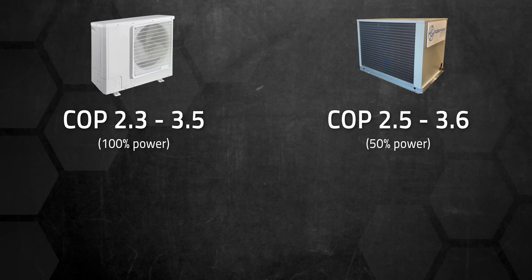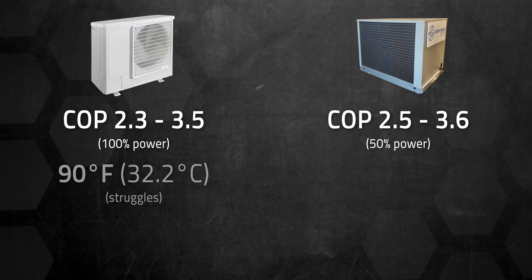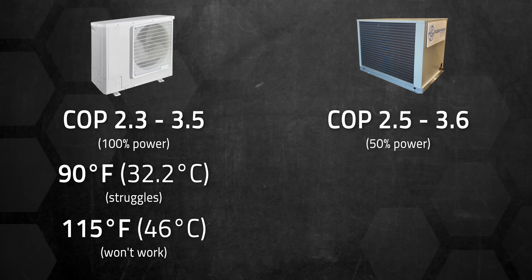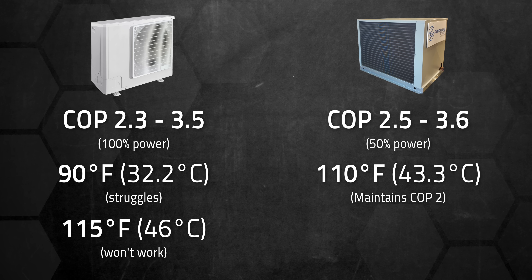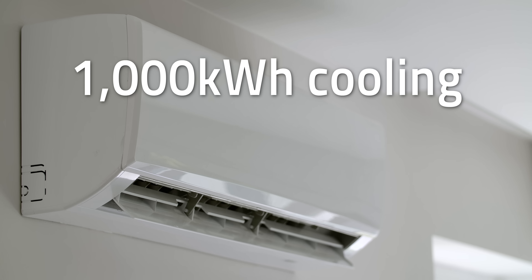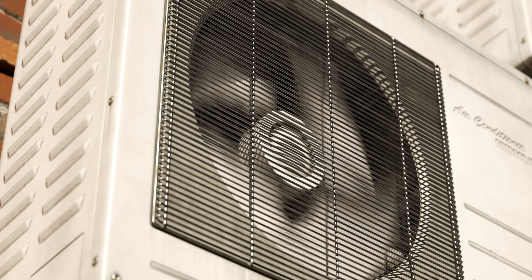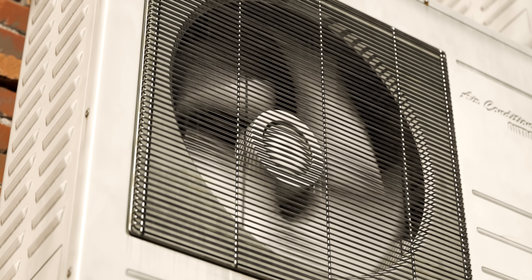Also, being a heat pump, it works in reverse too, taking extreme temperatures of around 110°F or 43.3°C and cooling them down to a much more comfortable range, all while maintaining a COP of 2 or more. Fluid claims the system can handle really extreme temperatures of up to 130°F or 54.4°C, and their president Ben Schwartz told me that they've tested it all the way up to 140°F or 60°C. Working at crazy high temps like that does cause Fluid's COP to dip below 2, though if it's that hot outside, we've got bigger problems. For comparison, your average residential air conditioner hits a COP of about 2.3–3.5 in mild temperatures. It really starts to struggle above 90°F or 32.2°C and flat out won't work above 115°F or 46°C. At higher temperatures of 110°F and above, Fluid can maintain a COP around 2, providing a good buffer in summer months where heat spells are becoming more common.